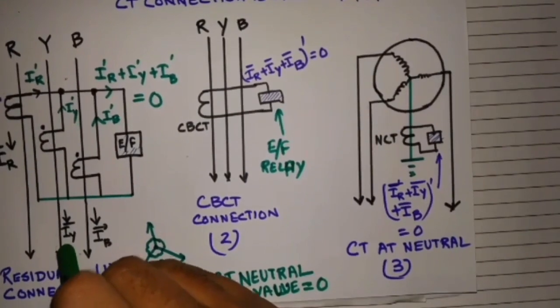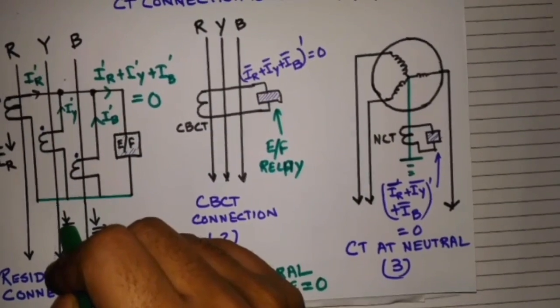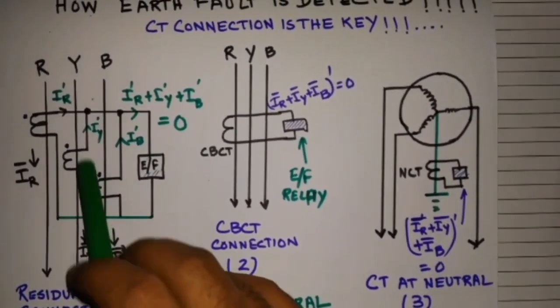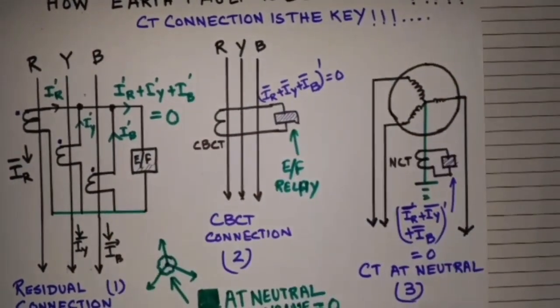If there is a two-phase to ground fault, suppose these two phases have faulted and connected to ground, then IR and IY will have value and IB will be zero, but their summation will not be zero. So in that case the relay will also pick up.